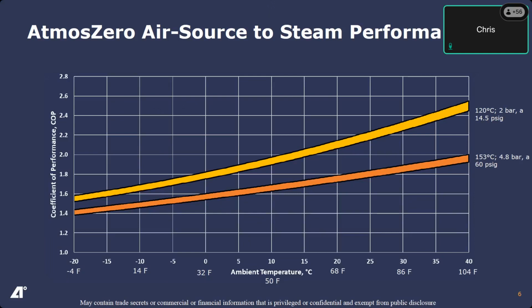You can flip to the next slide. So here is the money slide, if you will, for most engineers. They're very curious about the COP profile that we can do with our equipment. The x-axis here is ambient temperatures. So if you're an air source system, you're going to walk up and down this curve throughout the year. The y-axis there is obviously the COPs. The yellow line on the top is probably more indicative of a building application. So that's about a 15 PSI discharge. And then the 60 PSI orange line is more in line with what you'll see in some processing, food, beverage, pharma type facilities.